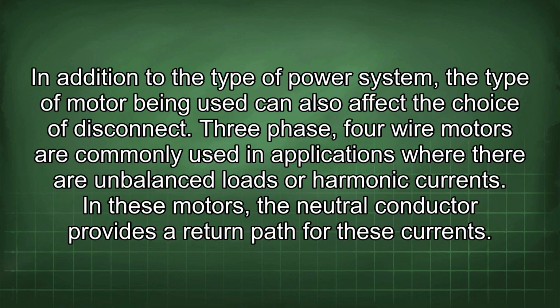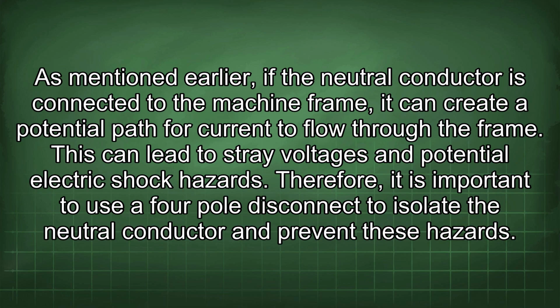In addition to the type of power system, the type of motor being used can also affect the choice of disconnect. Three-phase, four-wire motors are commonly used in applications where there are unbalanced loads or harmonic currents. In these motors, the neutral conductor provides a return path for these currents. As mentioned earlier, if the neutral conductor is connected to the machine frame, it can create a potential path for current to flow through the frame. This can lead to stray voltages and potential electric shock hazards. Therefore, it is important to use a four-pole disconnect to isolate the neutral conductor and prevent these hazards.